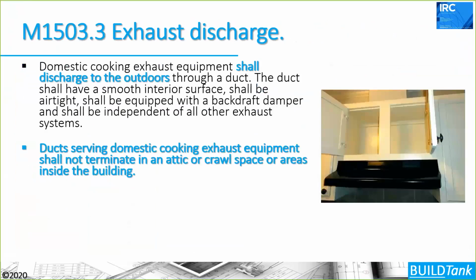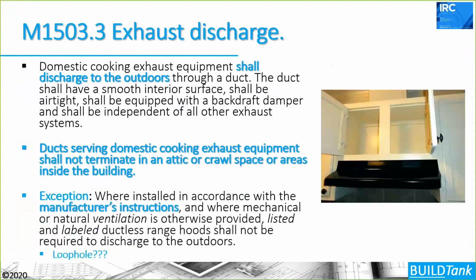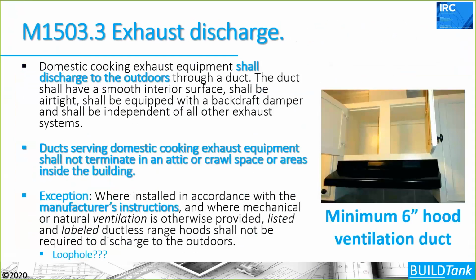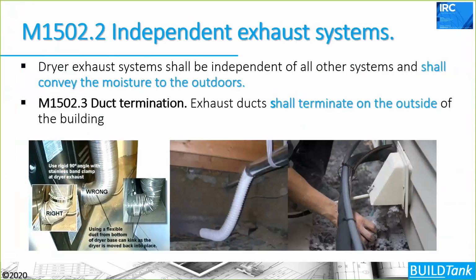This includes, in this program, the range hood. Even though there is this loophole, in this program, the range hood needs to be ducted to the outside. And at a rough stage of construction, it's often really good to verify that you have at least a 6-inch duct that's going to duct that range hood to the outside. If you're using some of these commercial quality hoods that push really ungodly amounts of air, like 1,000 CFM, 1,500 CFM, you're going to need a larger duct than six inches. But at a minimum, a 6-inch duct needs to be installed.